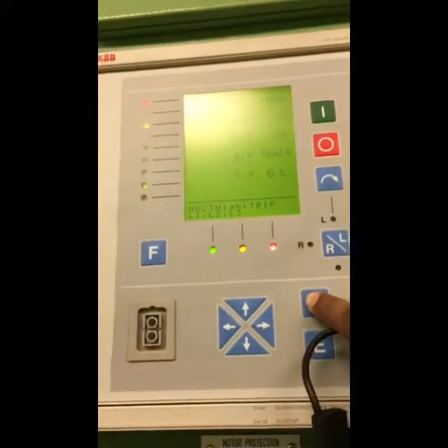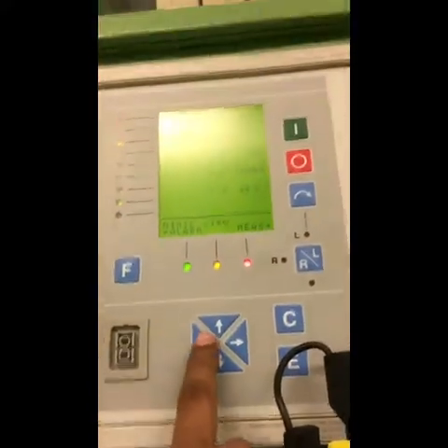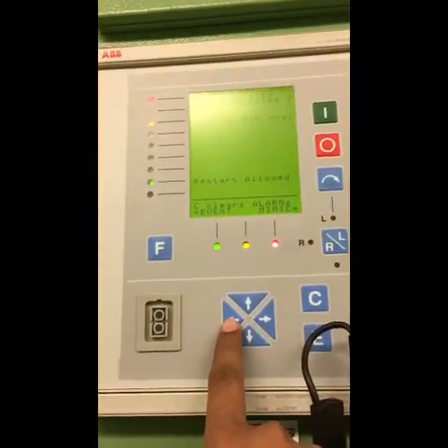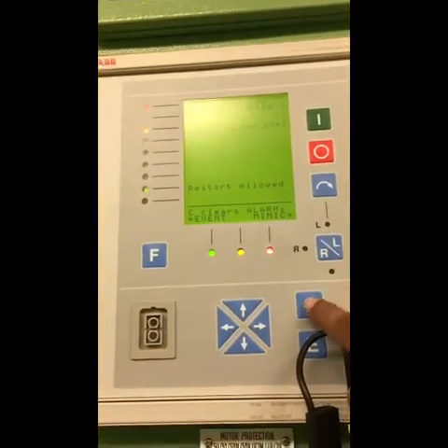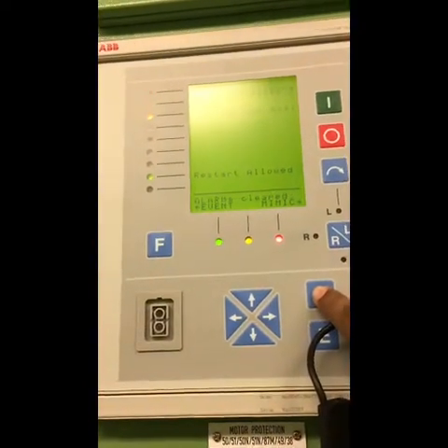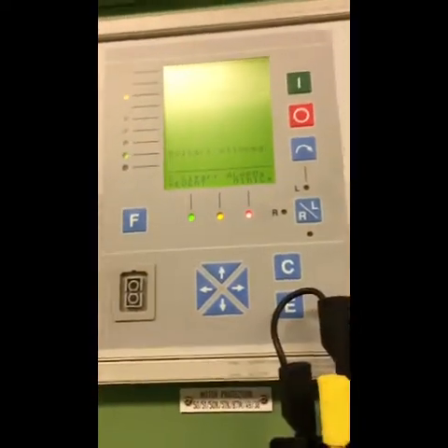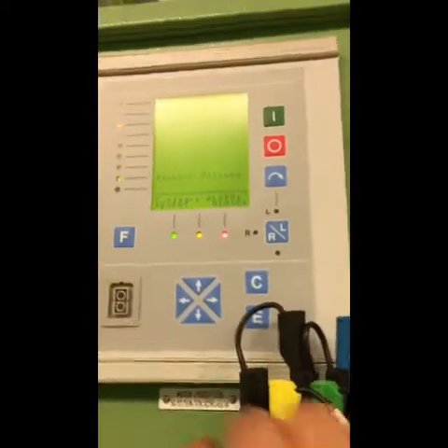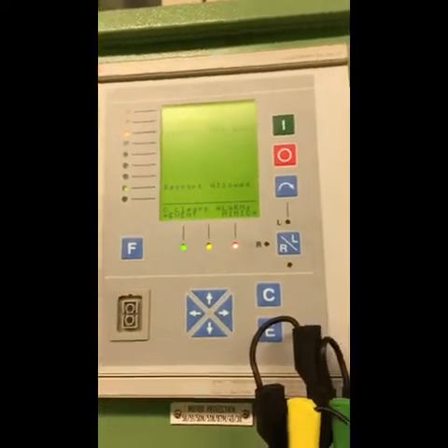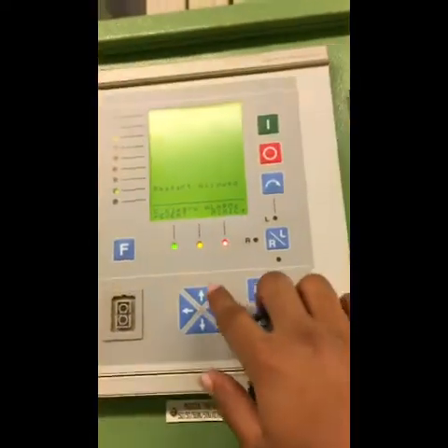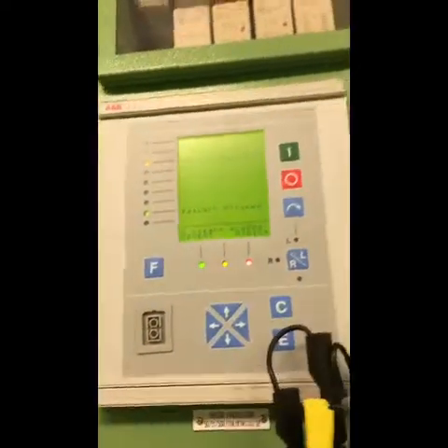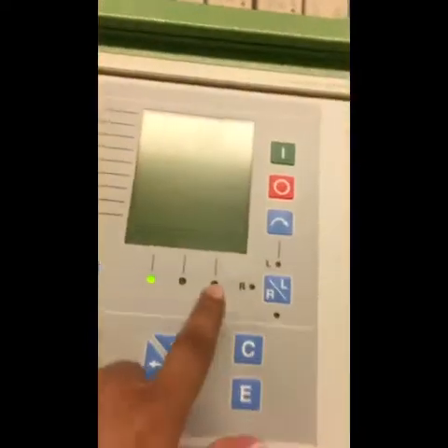First, I will reset the indication. Then I will have to go left. These are the alarms. Now I am going to reset the alarm. As long as the blinking is gone, it will be reset. Now because the breaker is racked out, this indication should not be here because we are in annual outage and the breaker cubicle is not available. This relay, as you can see here, says cubicle not available. That's why there is this indication, but in normal condition it should be like this, no red indication and no alarm indication.